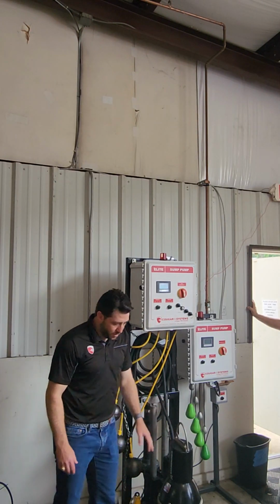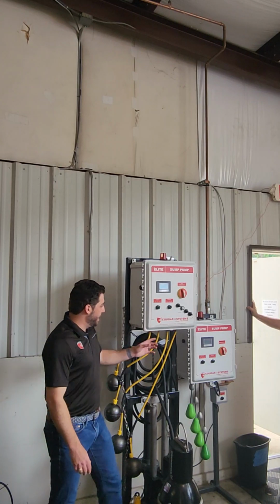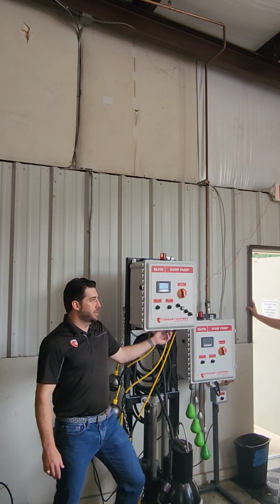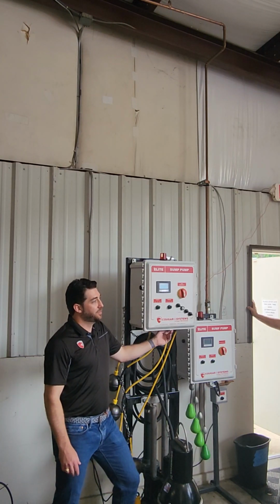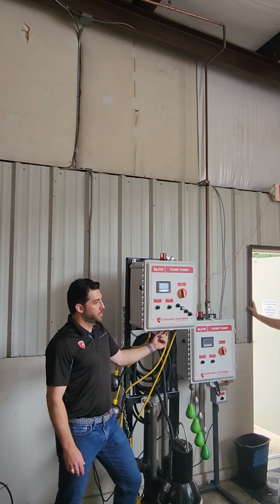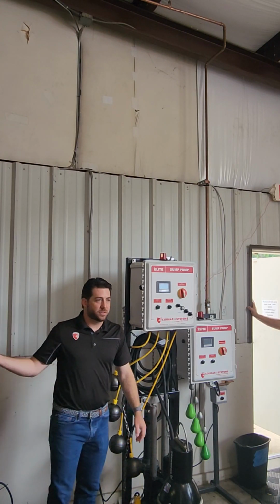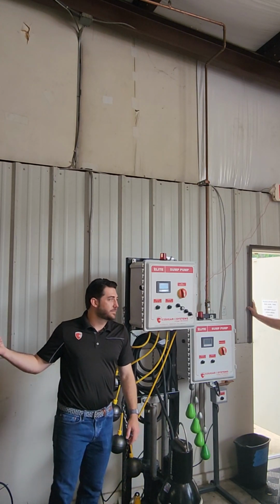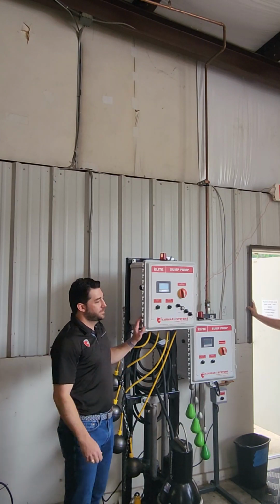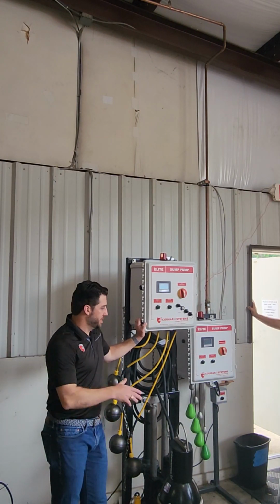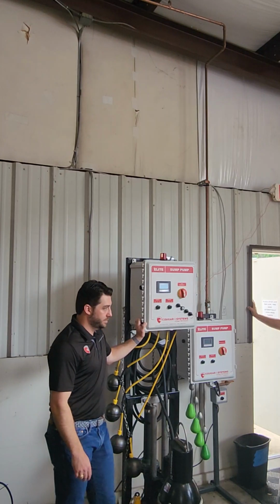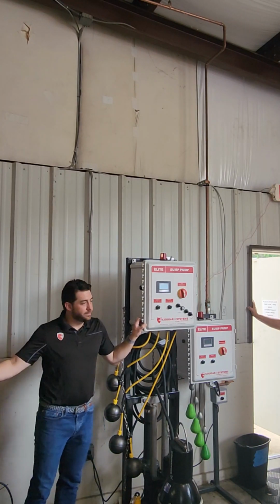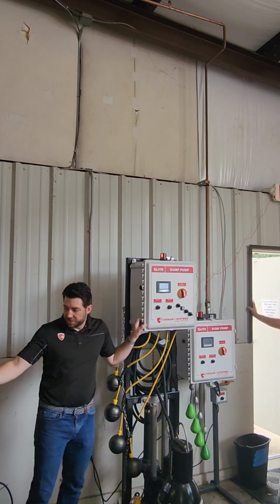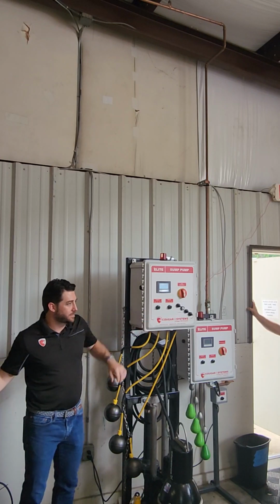So the warranty's the same. Good question. We have seen better life out of the floats on this one because we're doing 24 volts to the floats instead of 120 volts off of those. It's not so much wear and tear on it. Okay. Floats are rated for it, but it's a lower voltage. Can you use those on a 24? Yep. Most of the time we're using these floats on this panel.